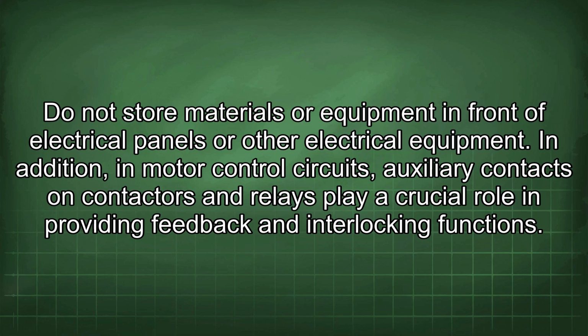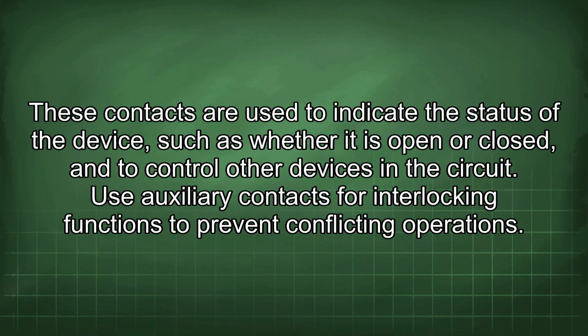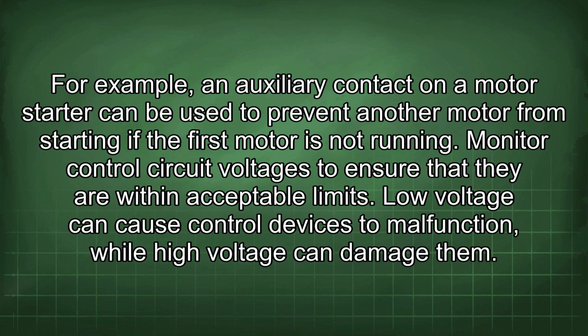In addition, in motor control circuits, auxiliary contacts on contactors and relays play a crucial role in providing feedback and interlocking functions. These contacts are used to indicate the status of the device, such as whether it is open or closed, and to control other devices in the circuit. Use auxiliary contacts for interlocking functions to prevent conflicting operations. For example, an auxiliary contact on a motor starter can be used to prevent another motor from starting if the first motor is not running.